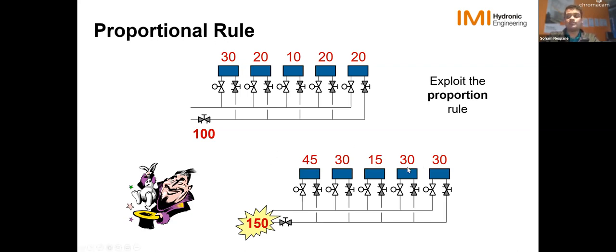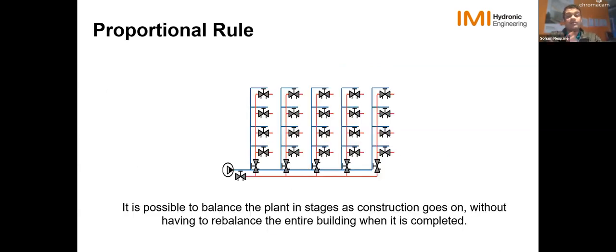That's great because now they are all proportional. If I lower this down to 100, all of these will go down by the same proportion and get back to the exact same flow rates that you saw. So that's the proportional rule, which helps us create these independent modules, even using manual balancing. Say you have a building with phased construction going on. You've got your partner valve and your terminal units, and you can balance this. What we're doing with the partner valve is making this independent of the changes from the rest of the system, because all of that only affects your partner valve, and this works as a single unit that we can control. Simply by throttling our partner valve, we are able to control the flow by the exact same proportion on each of these, rather than having to go to every individual one.